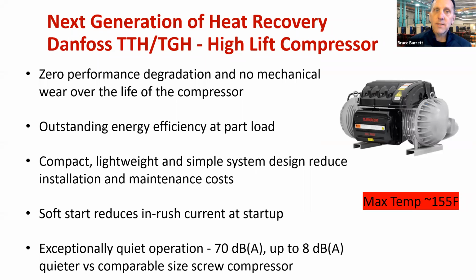So last week we did talk about our TTH, or our high lift magnetic bearing chillers, and how they were employed in air-cooled chillers with very high ambients. Texas, Oklahoma, Phoenix, Arizona. We use that high lift compressor anytime we get around 110 ambient. Why? Because that compressor has a very high pressure ratio. It can have very hot discharge temperatures to the condenser side. It's still very compact and lightweight.